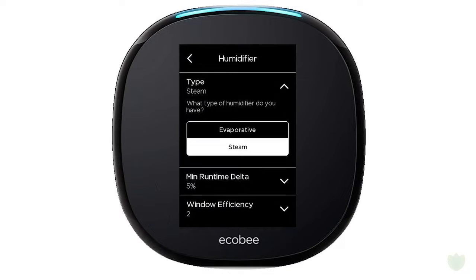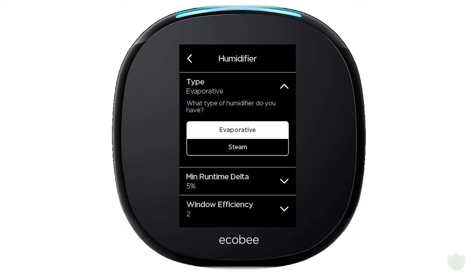So one little thing that I always like to talk about in our trainings is with the humidifier, you basically always want to choose the steam setting, because if you're using evaporative, what that means is the humidifier is only going to run during a heat call. So that humidifier accessory will only kick on when the furnace is running, basically, if you're using evaporative.